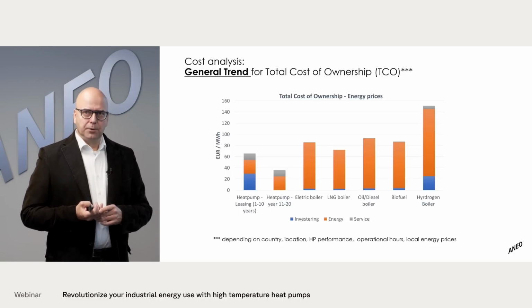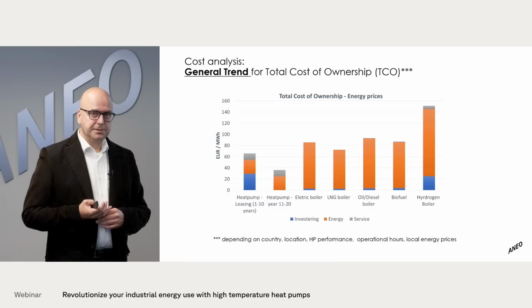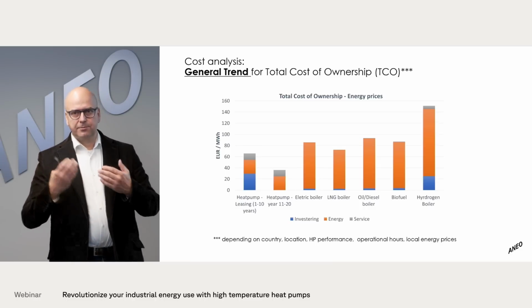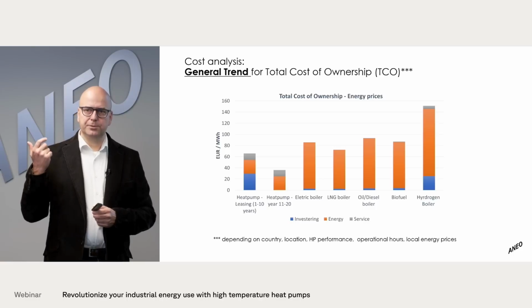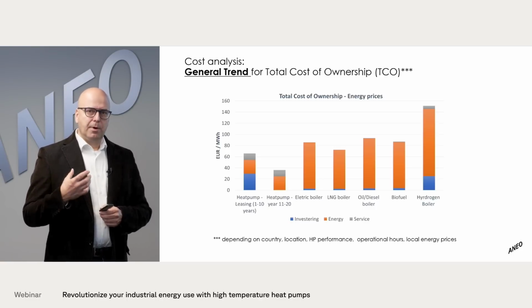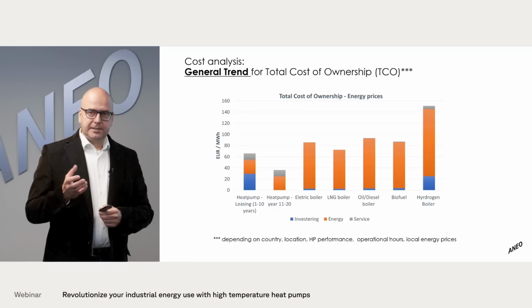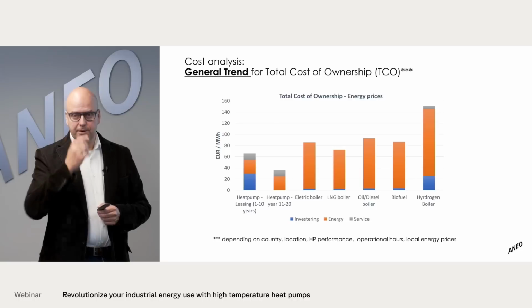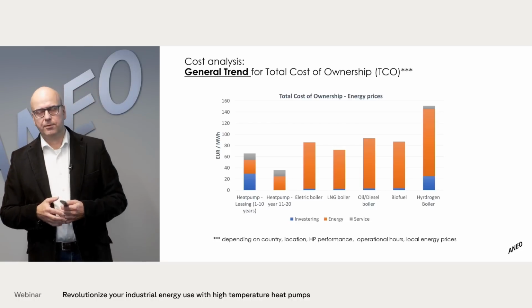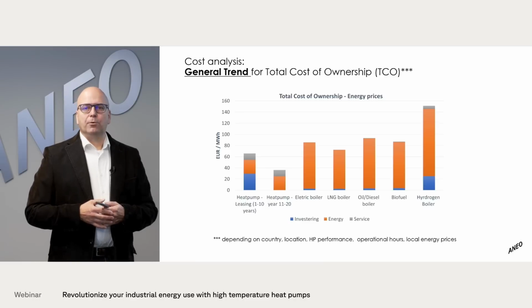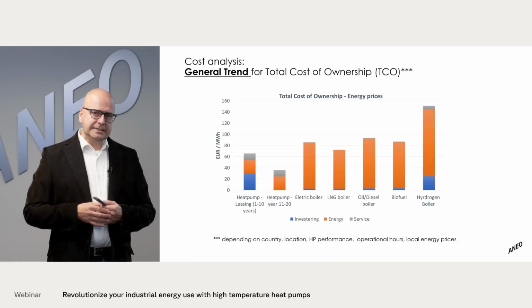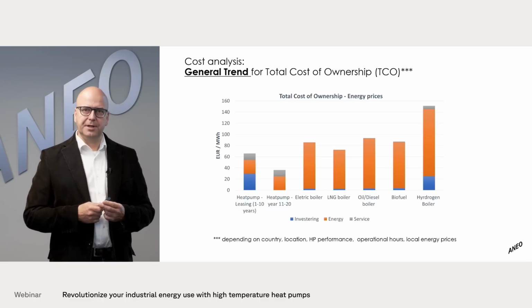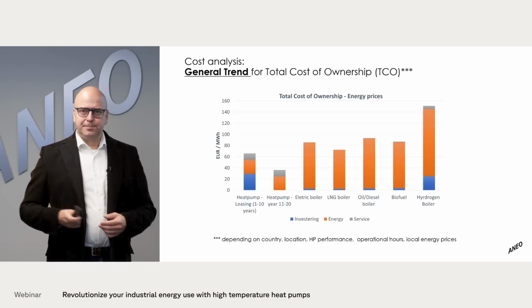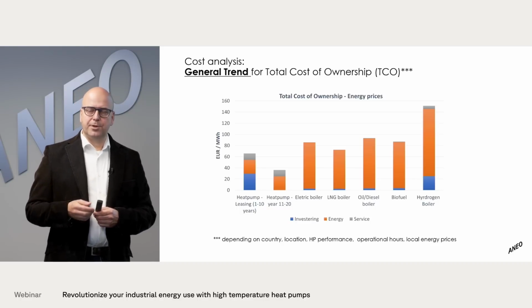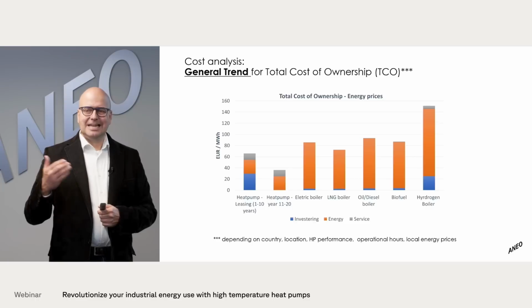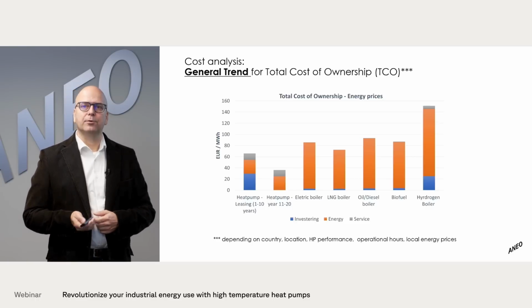Last but not least, in this total cost of ownership we also see service costs are higher for heat pumps. But if you put these three cost elements together - investment, primary energy use, and service and operational costs - the heat pump is more competitive on pricing than most other technologies. For this graph, I must be honest, I chose an example very beneficial for heat pumps: a large system around 5 megawatts, operating around 7,000 hours per year, using the energy price from 2 or 3 days ago. Since energy prices are always changing, this graph changes too, but it gives a general impression of how heat pumps can be competitive compared to other technologies in the market.